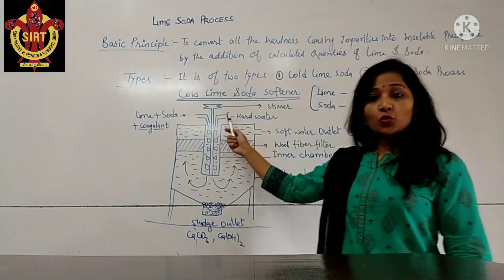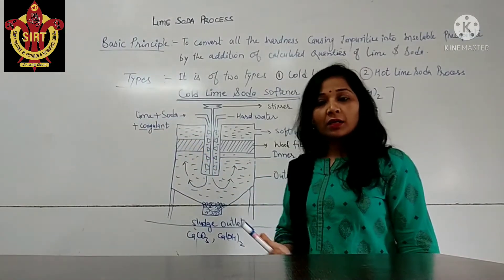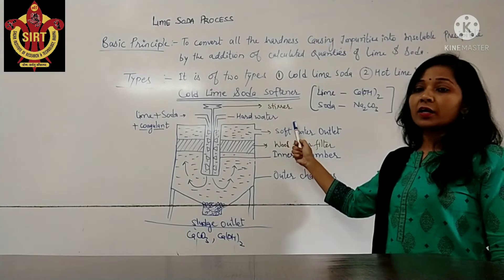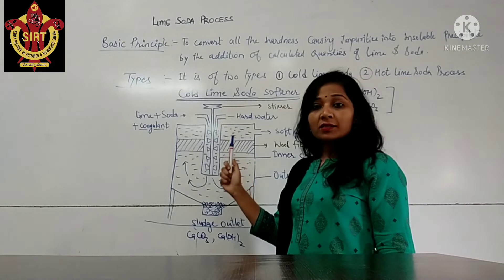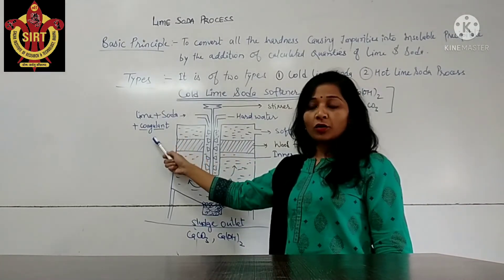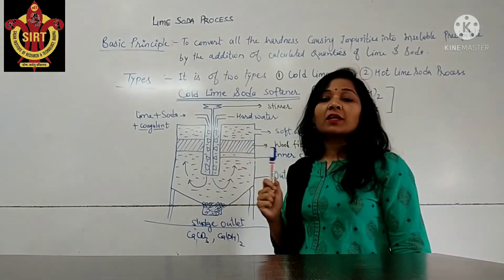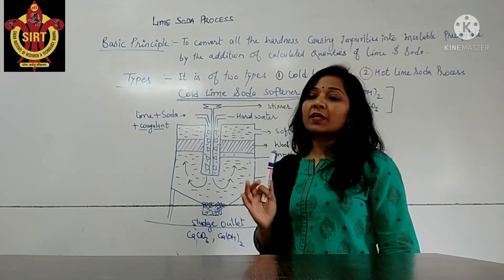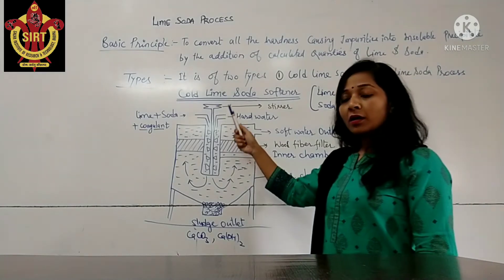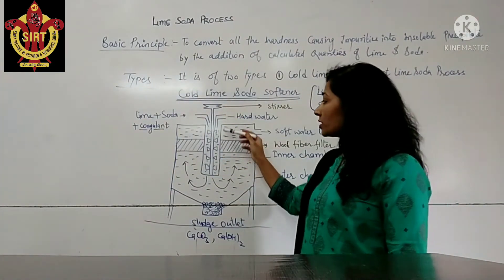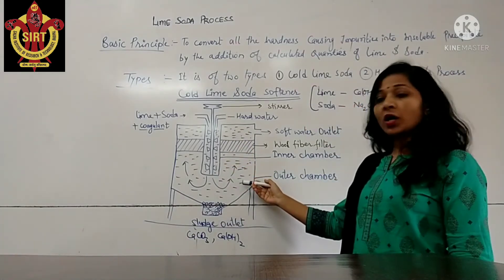In the inner chamber there are two inlet valves: one inlet for the addition of lime soda and coagulant, and the other inlet for the addition of hard water which is to be softened. When the mixing of lime soda, coagulant, and hard water takes place, continuous stirring and mixing causes a reaction between them and the precipitate formed comes outside the inner chamber. When the reaction completes, the water comes out of the inner chamber into the outer chamber.